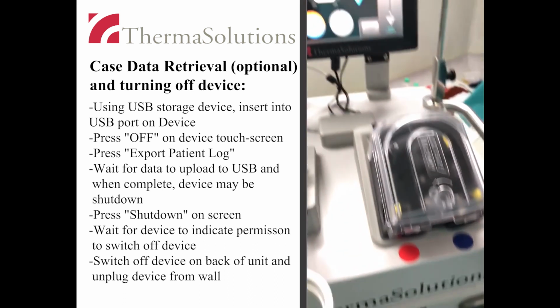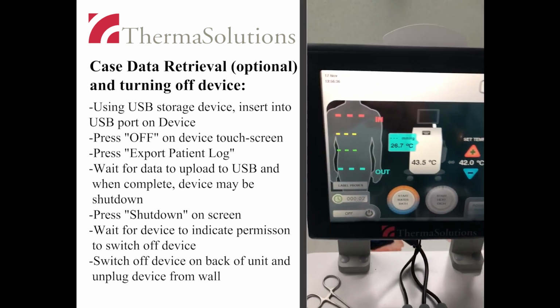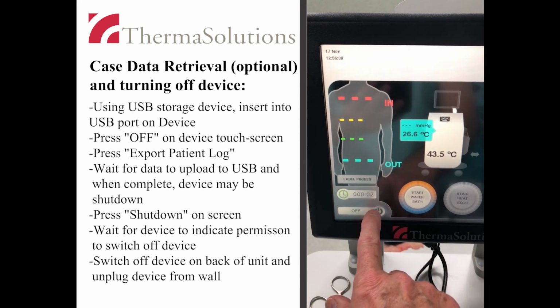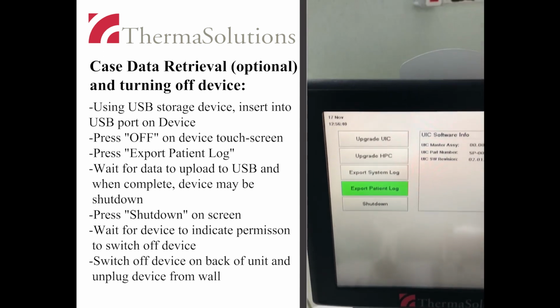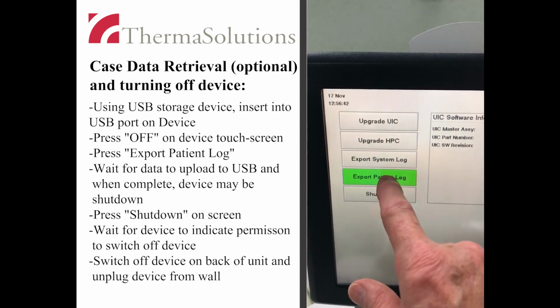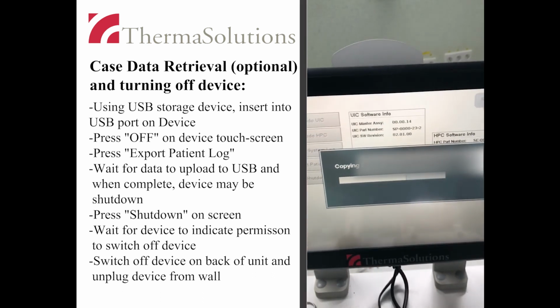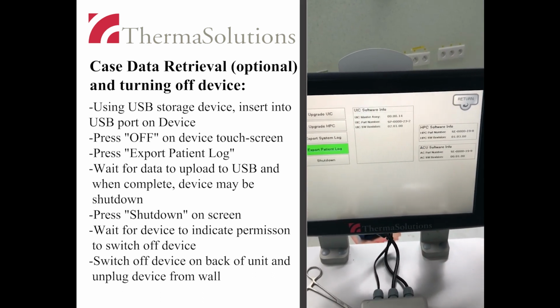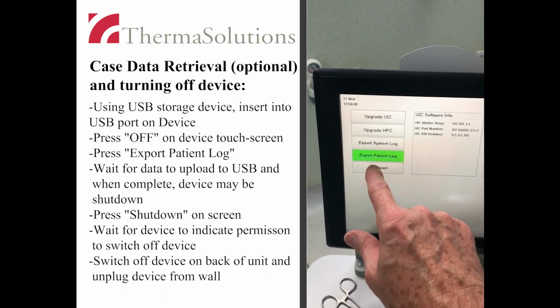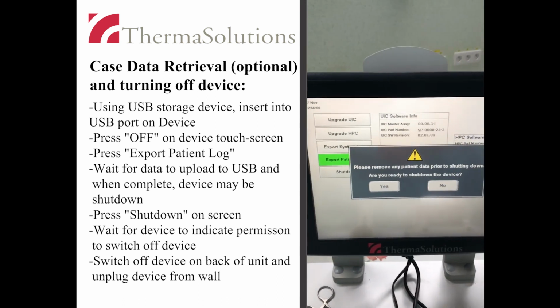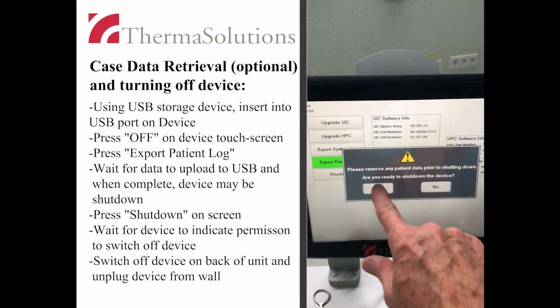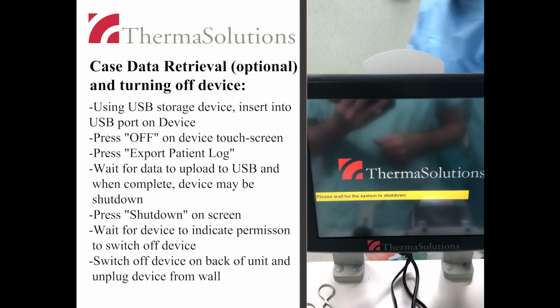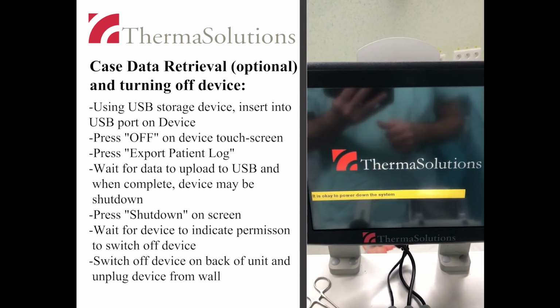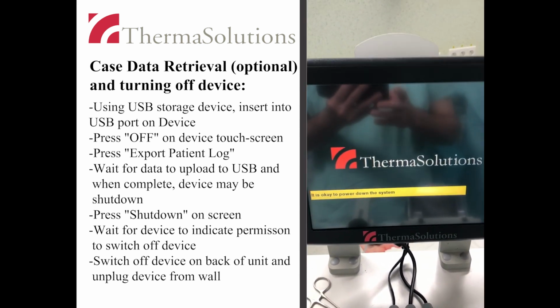If case data retrieval is desired, insert a USB storage device into the USB port on the connector panel. Touch the off icon on the home screen to initiate the data retrieval. On the next screen, press Export Patient Log and wait for the data to upload to the USB storage device. When the upload is complete, power down safely by touching Shutdown on the screen. Wait for the permission message before switching off the device on the back of the unit.